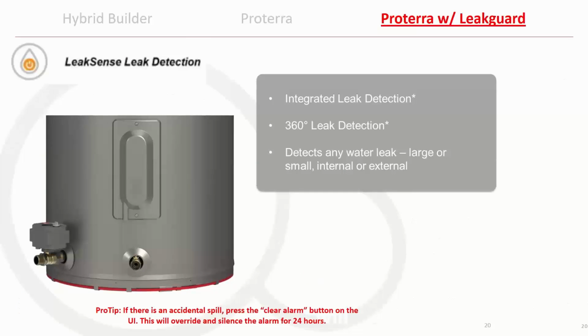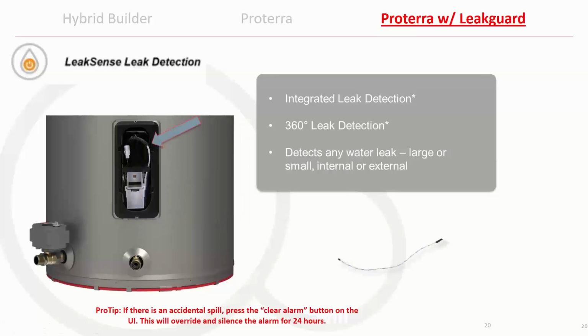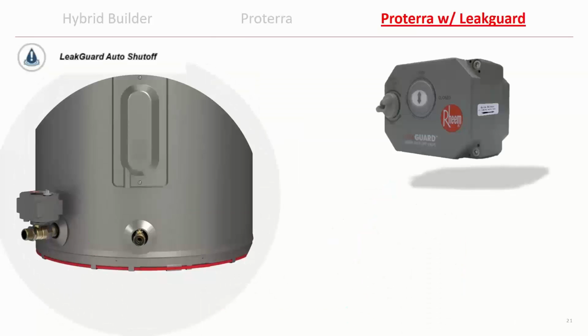All right, integrated leak detection. The way we do it on the one with leak guard, if you order it with everything on it, as you can see down here, you see this red band running around there. That's actually a wick at the bottom that runs all the way around the heater. That white rope is inside and is channeled down into that wick. We're showing you right there. Now, if there's a leak detected in that wick, anywhere around there, that wick's going to pick up that water and it's going to bring it to that white rope and it's going to say, hey, we got a leak.